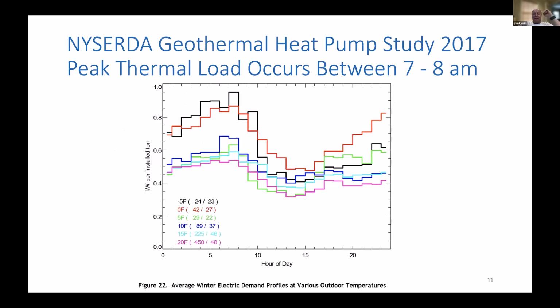This is the profile from the heat pump study done by Hugh Henderson for NY-GEO. You can see here nicely, this is the peak profile of 17 buildings across the state. These are residential systems, and it shows that the black curve is at about -5 degrees peak temperature, the red curve is at 0 degrees, and then 5 degrees. So the warmer it gets, the lesser amount of kW the heating systems are using. But it also shows this is totally outside temperature dependent, which we would expect.